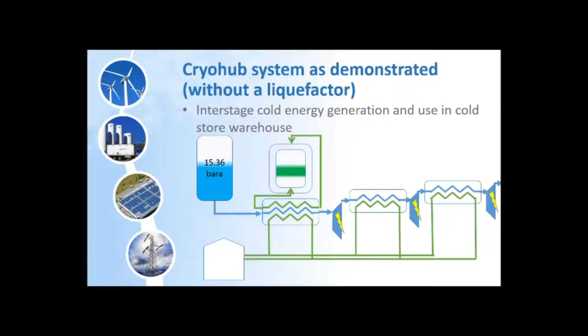So after talking with the heat exchangers manufacturers, we had an initial performance bid from them, and we calculated with the pressure drops provided that the inlet pressure to the first stage would be about 14.7 bars absolute pressure at -7.5 Celsius turbine inlet temperature. On the outlet, as there is expansion, then the temperature will drop to about -50 Celsius for pretty much all stages, with the pressure dropping about 2.3 times for each stage. The pressure ratio being about the same between the 3 turbines, meaning that the temperature on the outlet given the same inlet temperature will be similar, with a relatively small pressure drop interstage.